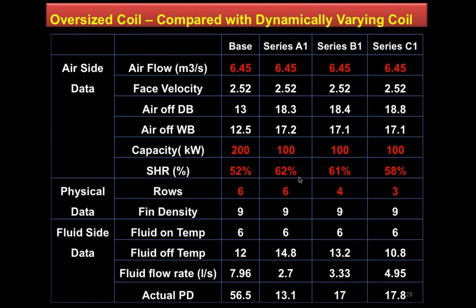We look at a hypothetical building where the actual peak cooling load is 100 kilowatts. The coil was selected to have a capacity of 200 kilowatts. So the oversized coil is 200 kilowatts. The actual coil I really need is only 100 kilowatts. The peak load is 100 kilowatts. Some basic parameters are listed here. Just a point I would like to make is that I'm going to make some of this information available to Tim, to be passed on to members later as handouts. So don't worry about some of the specifics and the details. You can pick it up later at leisure.